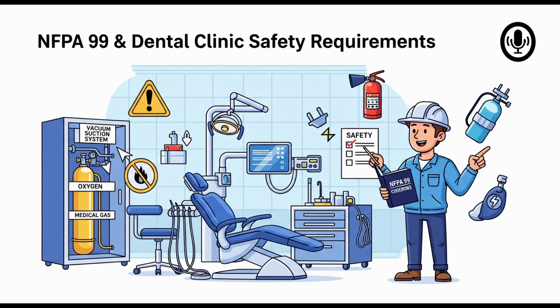This is all the commissioning process. Precisely. It often requires specialized certified personnel, sometimes a third-party verification company, to perform and document these tests properly. You need that formal verification that the system is safe and correct before it ever touches a patient.